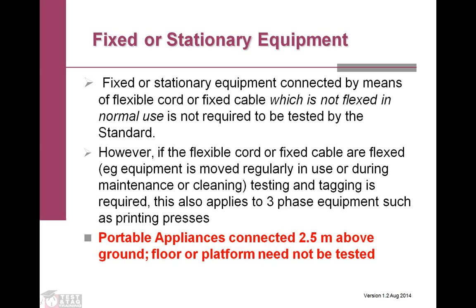And a lot of people are putting it into the printing environment. You might think you've got a large three-phase press that plugs in via a three-phase plug. That can still essentially be classified as a portable appliance and should be tested. And I can tell you firsthand, we've got three-phase presses that we've run over the journey, and the testing and tagging process can be a really important process for operator safety. We run tests on some of our presses where we've had multiple different parts to that press, and the reading will change depending on how many parts of the press you engage. If you've got laminating facilities or die cutting facilities or flexo or whatever, as you engage more of that machine, it can affect the reading on the tester.